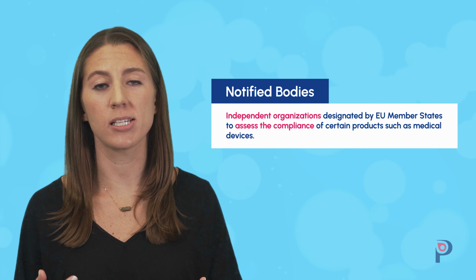Let's start by going over what exactly a notified body is. Notified bodies are independent organizations designated by EU member states to assess the compliance of certain products, such as medical devices. They evaluate various aspects of the product, including design, manufacturing processes, quality systems, and technical documentation to make sure they adhere to EU regulations and directives in what's known as a conformity assessment. Once a notified body determines that a product meets the required standards, it issues a CE certificate that allows the manufacturer to create a declaration of conformity and affix the CE mark to their product, demonstrating compliance with EU regulations.